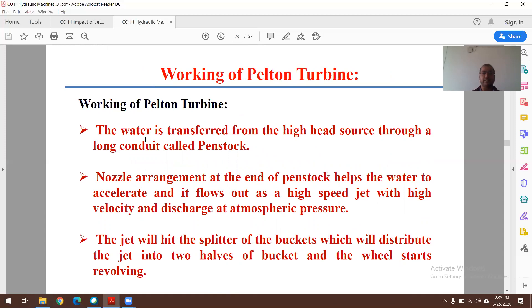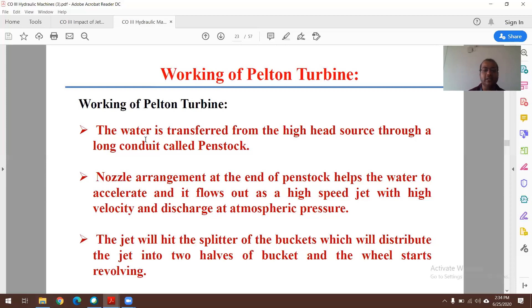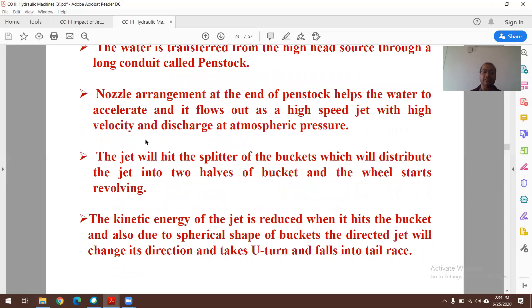For the working mechanism: water is transferred from the high-head source through a long RCC penstock. The nozzle at the end of the penstock accelerates the water, which flows out as a high-speed jet at atmospheric pressure. The jet hits the splitter of the buckets, distributing into two halves of the bucket, and the wheel starts revolving, driving the shaft. The kinetic energy of the jet is reduced upon hitting the bucket; due to the spherical shape of the bucket, the jet changes direction in a U-turn and falls into the tailrace.